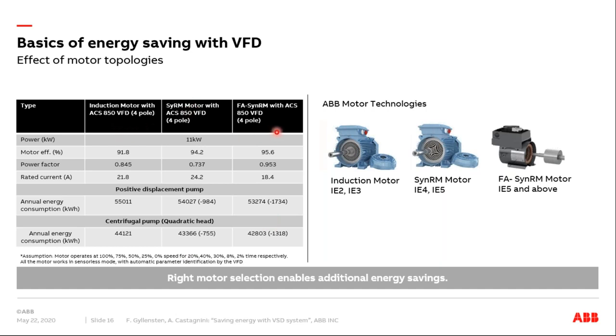All these motors are assumed to work in the sensorless control mode, with this ACS850 drive. You can identify the parameters automatically, so it's a very easy installation and ease of use. You just press a button, and the drive is intelligent enough to identify which motor it is, and all the motor parameters required are automatically identified by the drive.